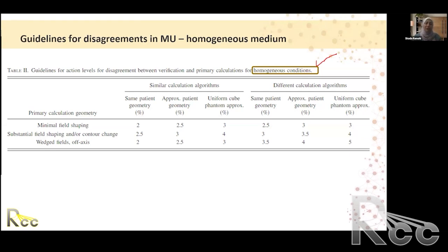First of all, is your patient all water? Is your patient homogeneous? And what are you using for calculation in your TPS? Now we look at what we are using for manual calculation. If everything is the same, and this will happen only for the TPS commissioning, right? We take data in a water phantom, and one of the initial tests we also do in a homogeneous medium when we're commissioning the planning system and verifying the output. Measurement is done in a water phantom, calculation in a nice cube phantom, and the physicist should expect, with minimal field shaping, a 2 to 2.5% discrepancy.